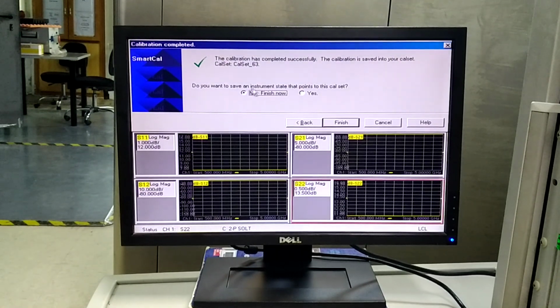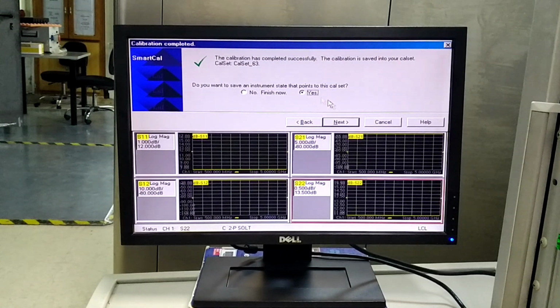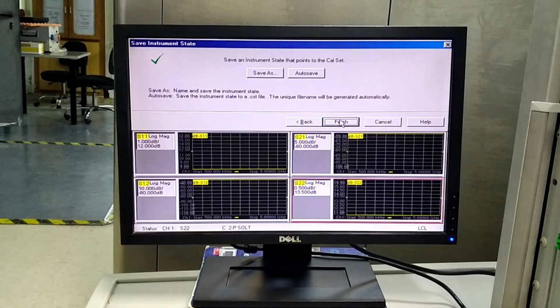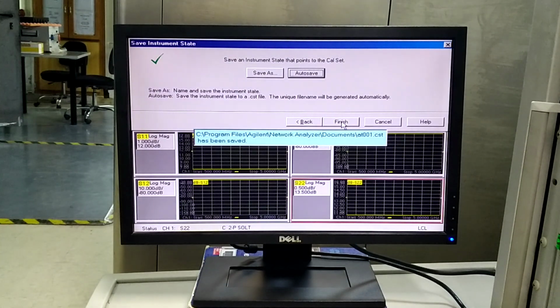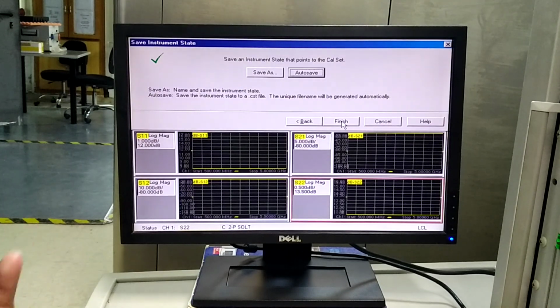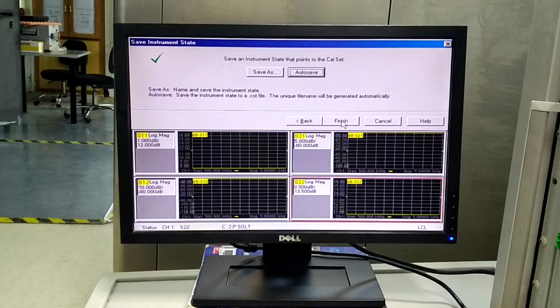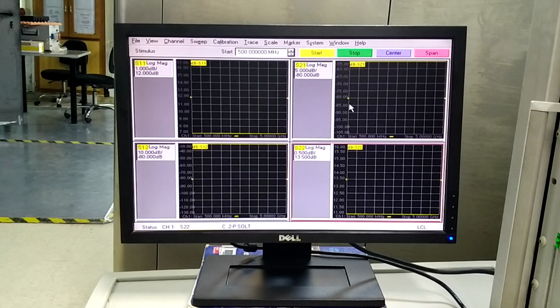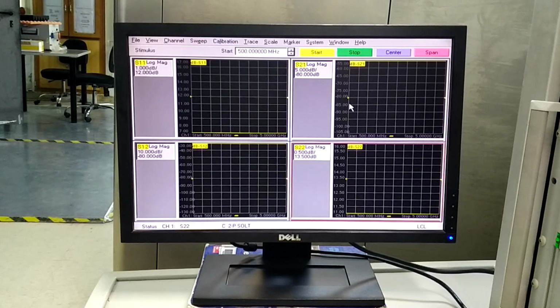So the next step: do you want to save the instrument state that points to the calibration? If you press the yes button, it saves this calibration kit to the database of the VNA. In our case, I press yes, and I just say auto save, and then it automatically saves this to the database, so in the future I can recall this calibration state as well. Then I press the finish button. So now the calibration has been performed.